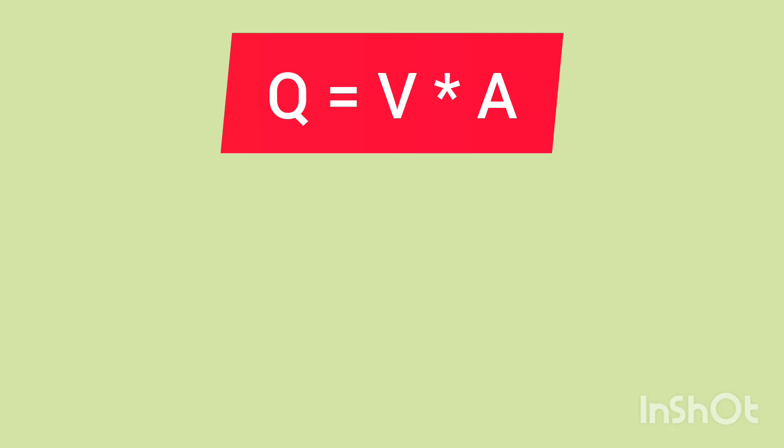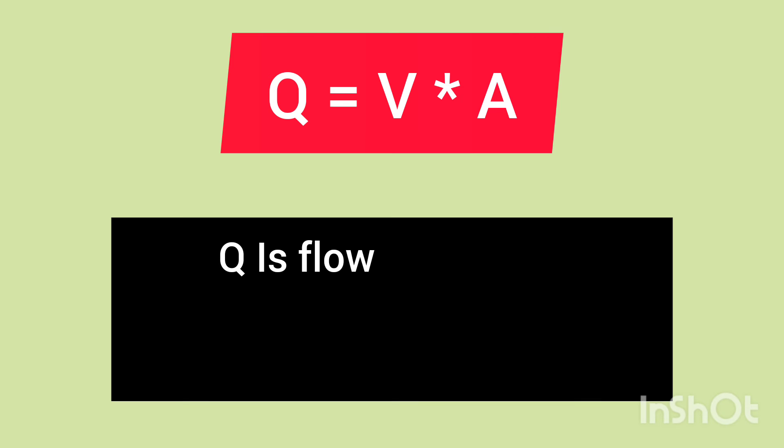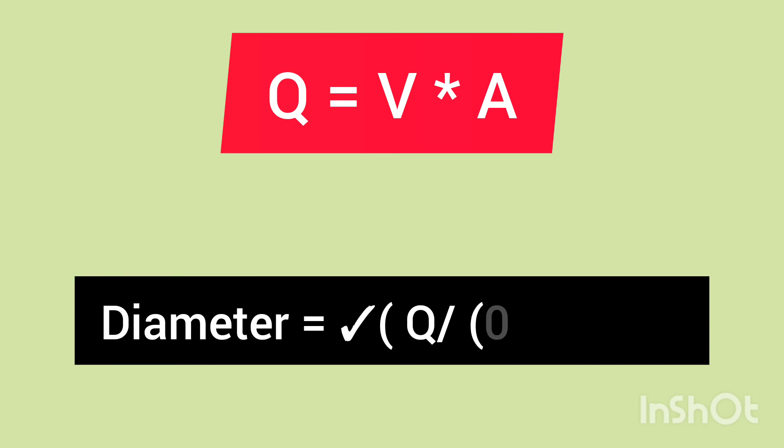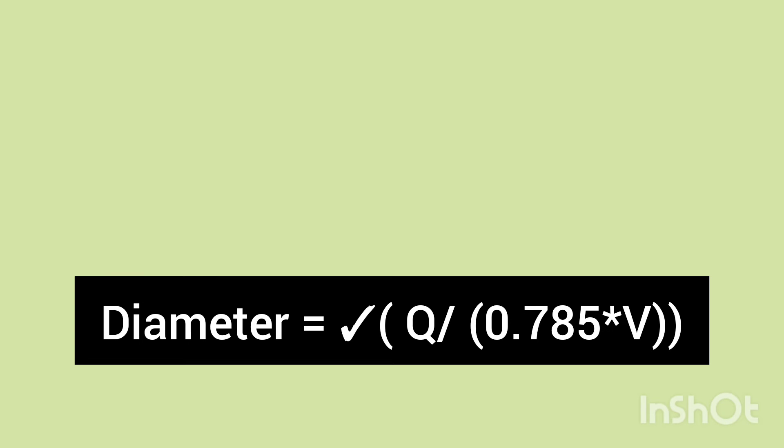Before we start with the example, we can rearrange this formula. Diameter equals square root of volumetric flow rate in cubic meter per second divided by 0.785 times velocity. 0.785 is the value of π/4.